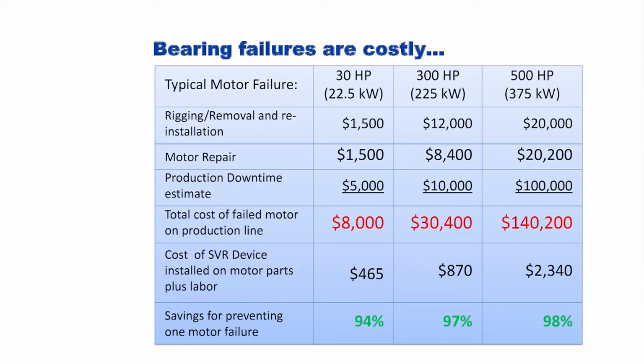The actual cost of the motor failure itself, total with the operation time, from $8,000 to $140,000, and that can seem extreme, but in a lot of cases that's very prevalent. The cost of putting a voltage reduction device in is minuscule, savings for preventing one motor failure, anywhere from 94 to 98% of the total cost.